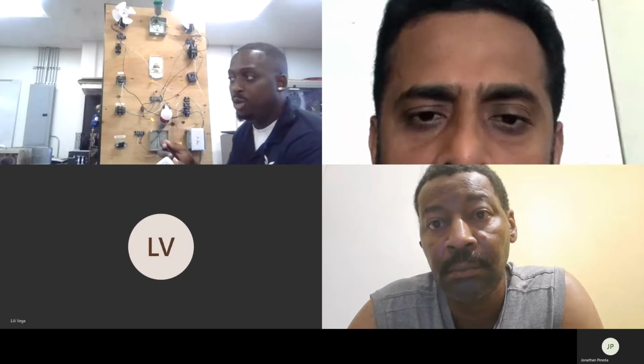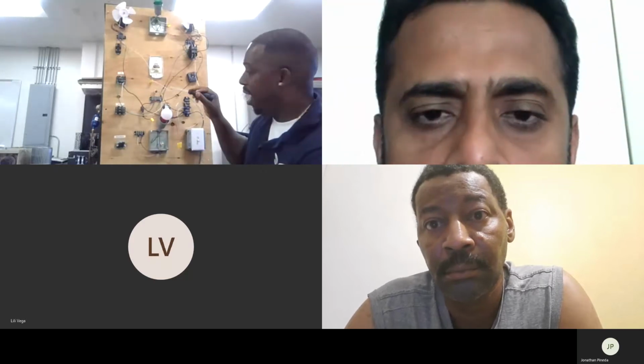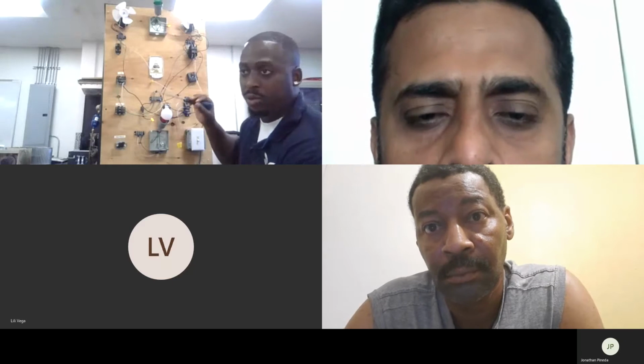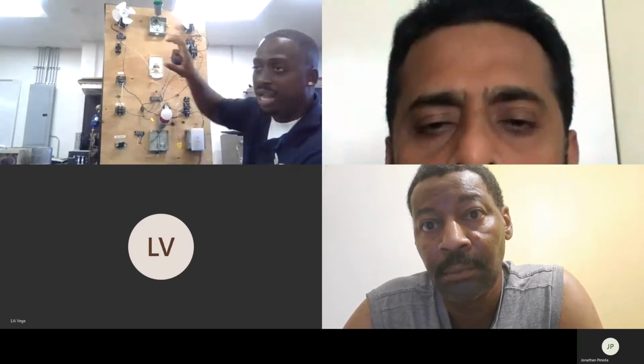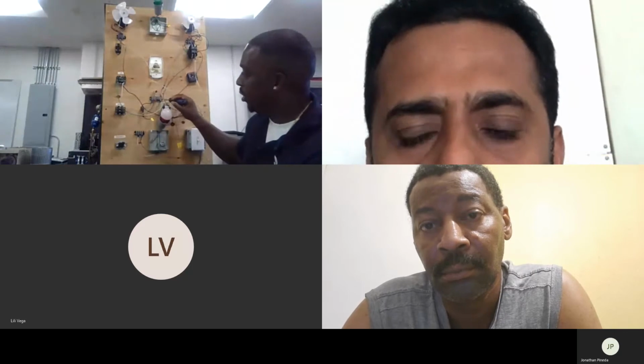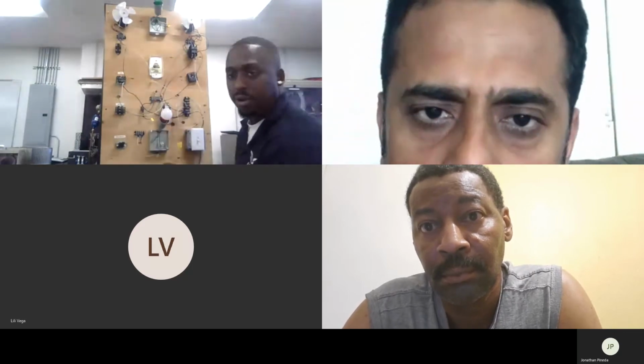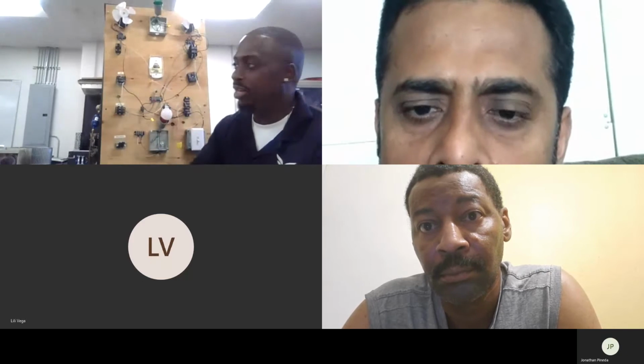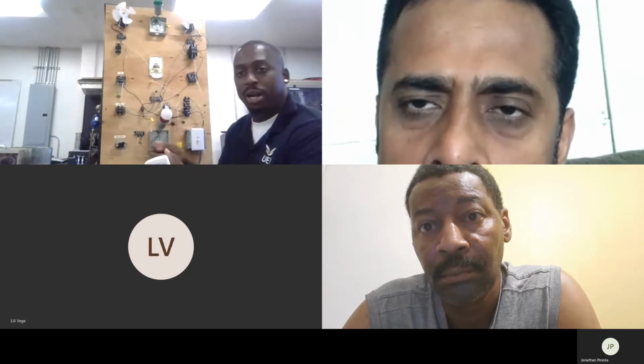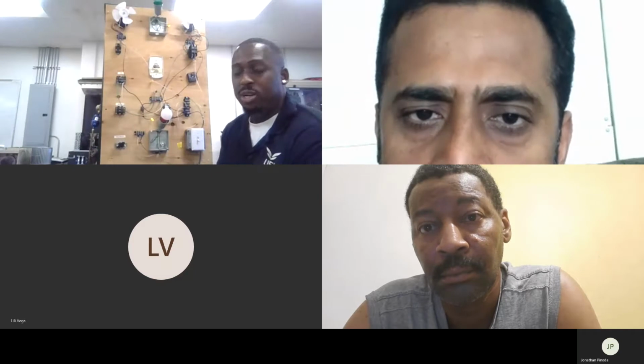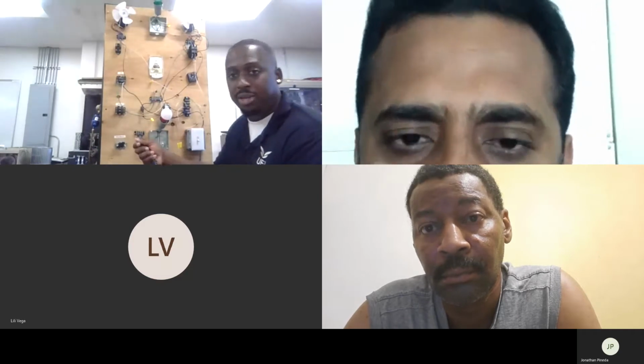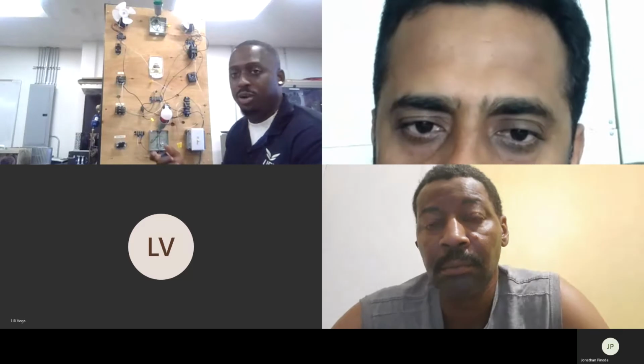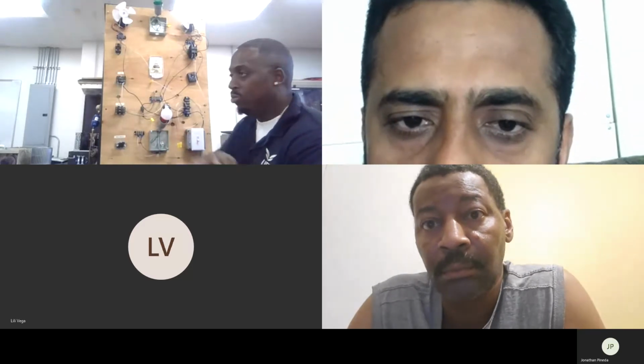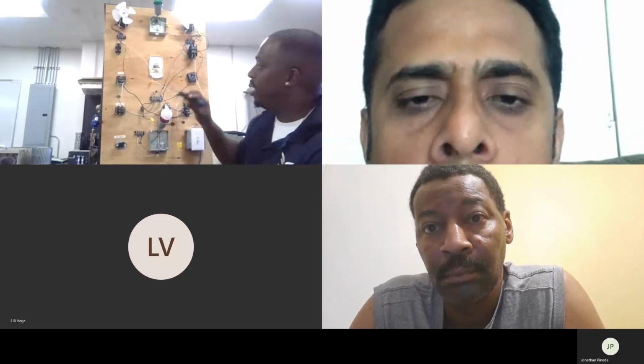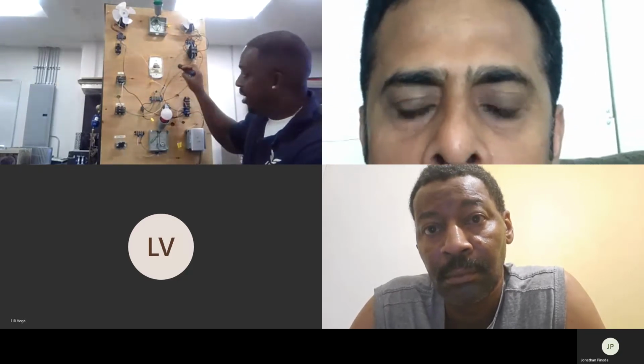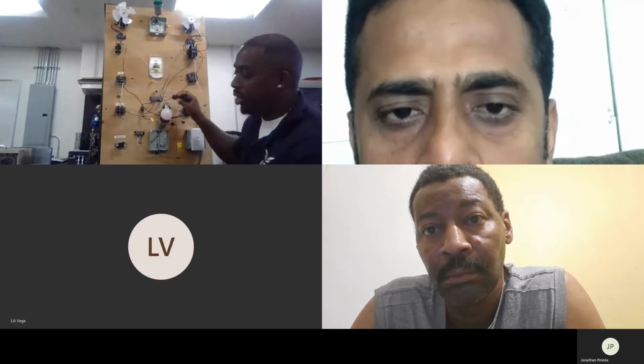If somebody went by color code but didn't realize how things were connected at the unit — because in real life, the thermostat will be in the living room somewhere, and this terminal strip we're connecting to will be on the circuit board inside the furnace. So if somebody downstairs at the thermostat wired it the regular typical way, putting R to red, but didn't know whoever was in the attic put the R to common — if he didn't know that and turned the unit on, now you've got a direct short. So regardless of the color code, you want to be sure that whatever combination is at your thermostat is the same as on your circuit board.